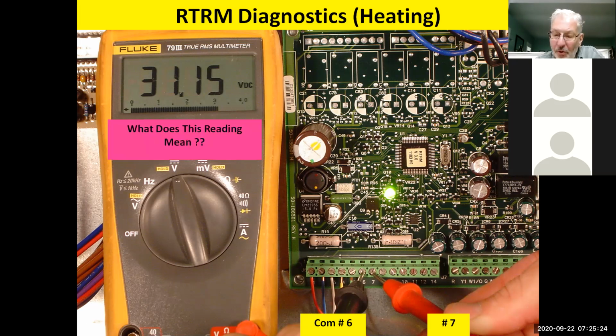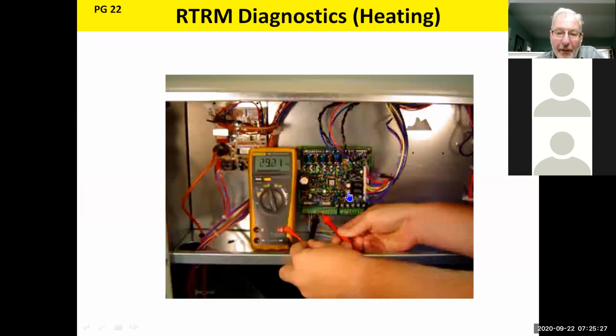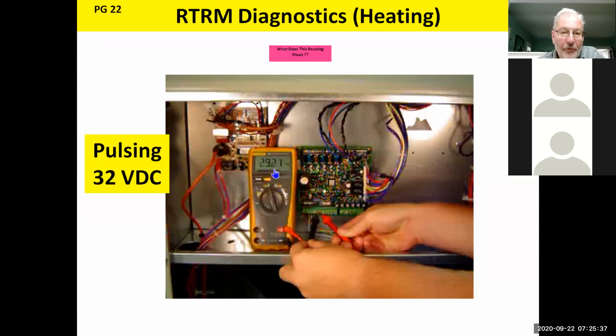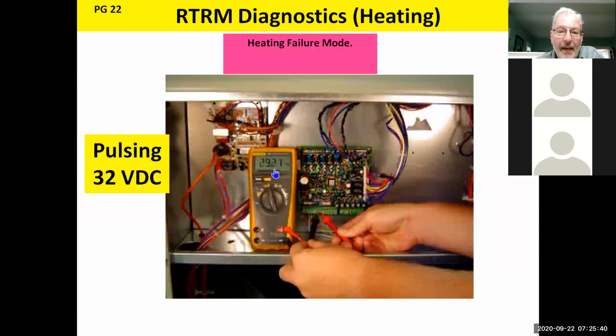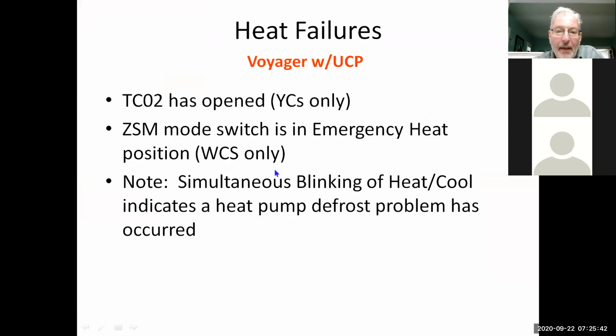If you go to that terminal and I'm seeing fluctuating voltage, if it's jumping up and down, if it's going 0 to 32, what that means is I'm in a heat fail, okay? And that's fluctuating 32 volts, and it's going to tell me I'm in a heat fail. And at that point, you're probably locked out. And the thing with these units is when they go into a heat fail, it shuts down the blower, the heating system. It locks the unit down. It's trying to protect the unit from overheating itself. And usually when you see that, it's TCO2 is open.